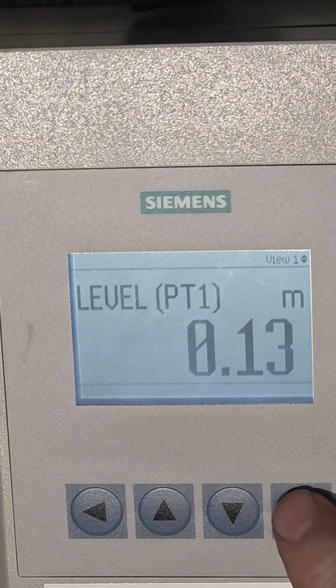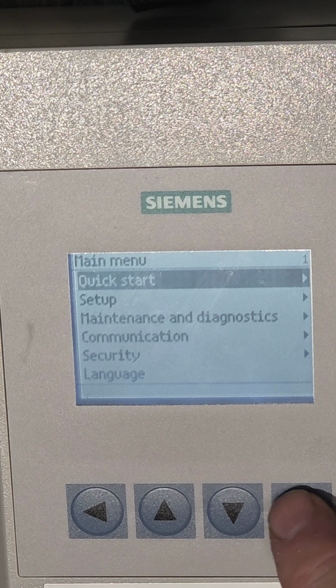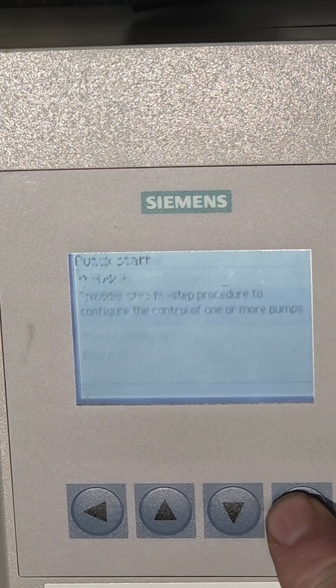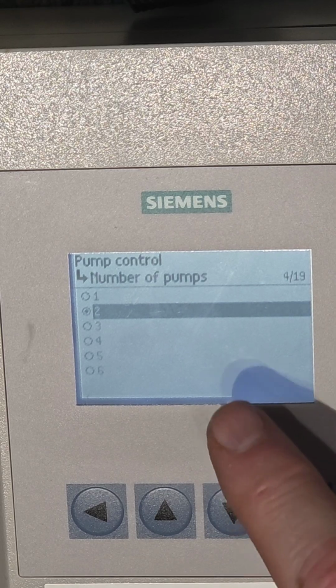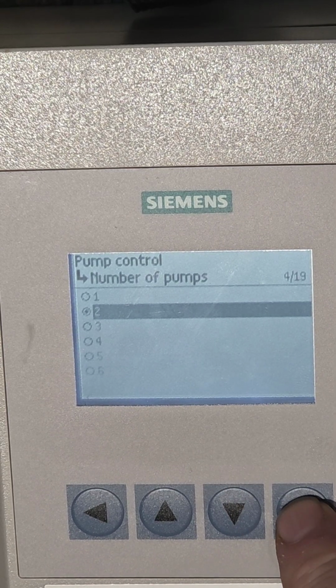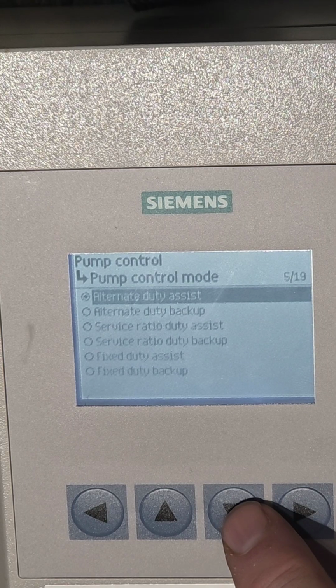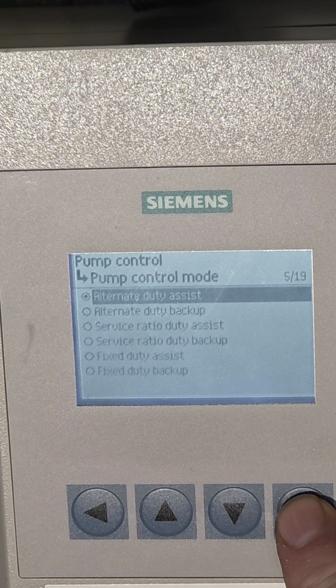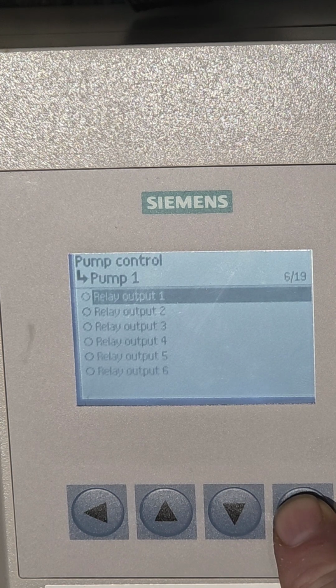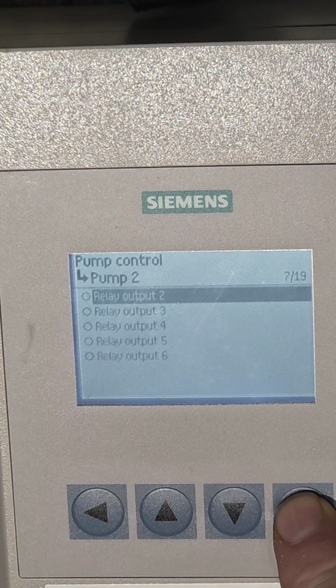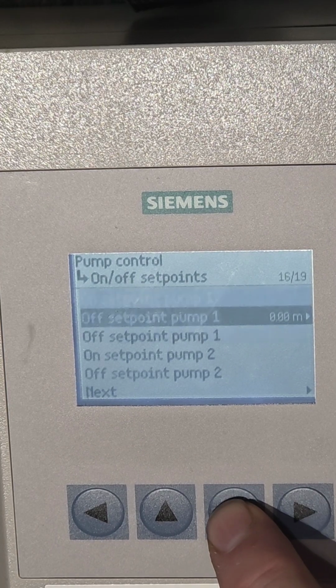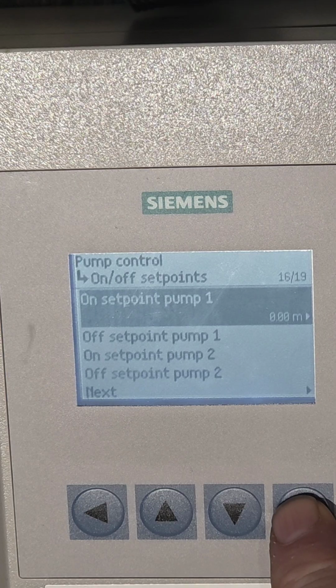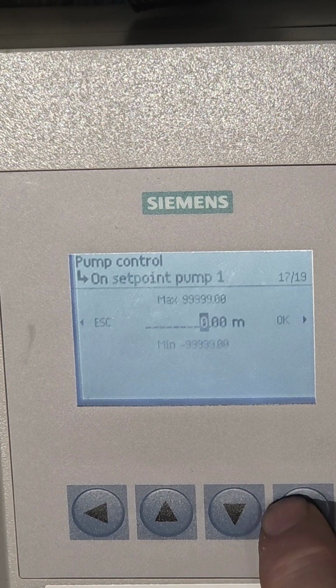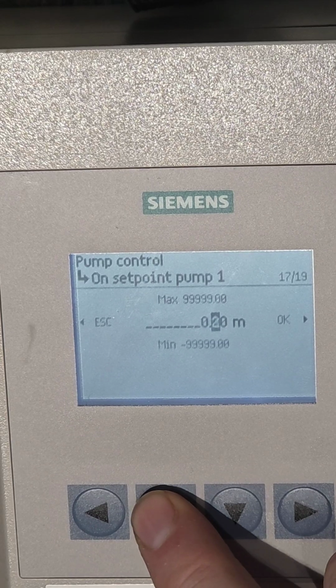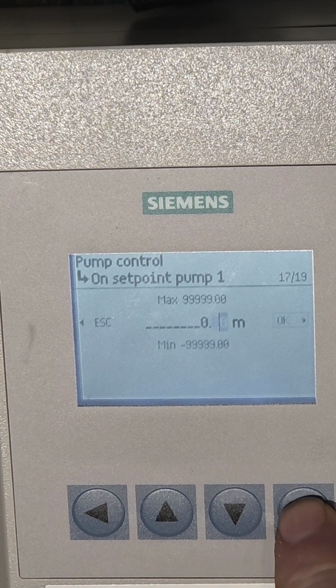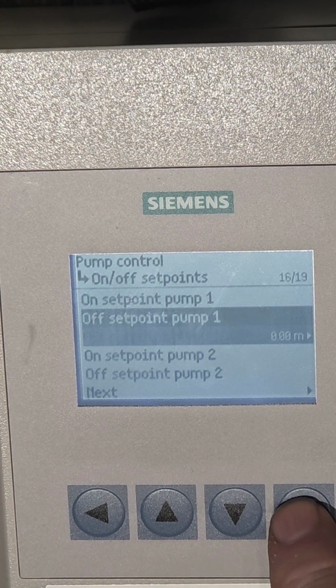Now we're going to set up the pumps. Quick start, down to pump control, right click again. Number of pumps, 2, that's already highlighted. And we wanted alternate duty assist, that's already highlighted as well. Pump 1, we're going to use relay 1. Pump 2, we're going to use relay 2. And the on setpoint for pump 1 is 0.8 meters. OK. And the off setpoint is 0.5 meters.